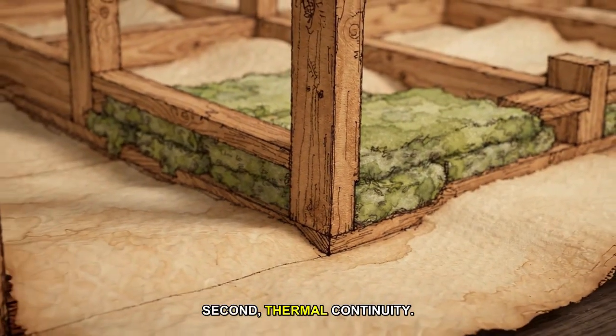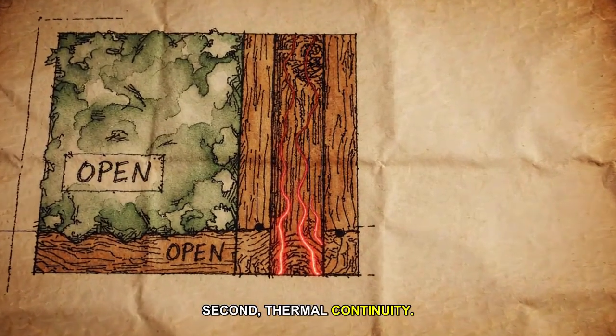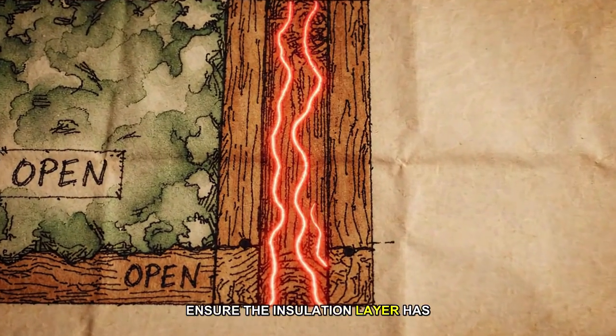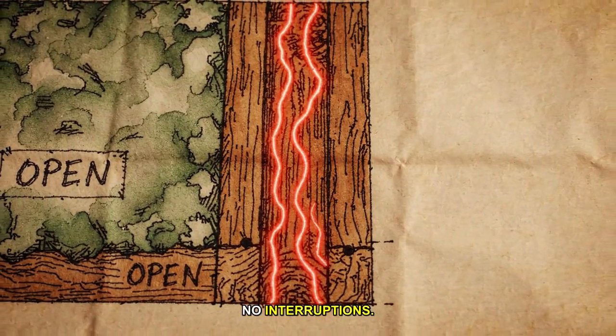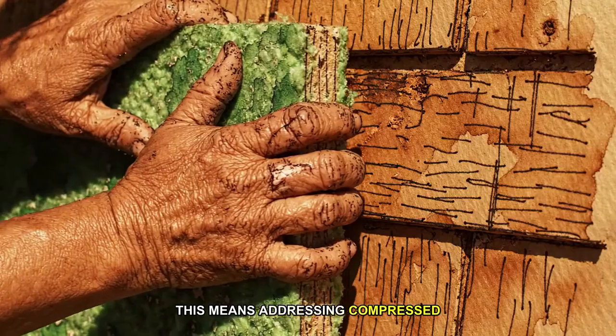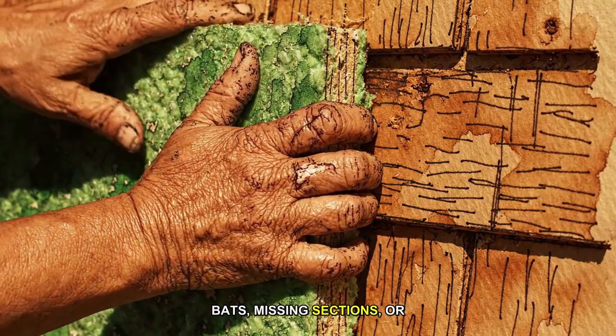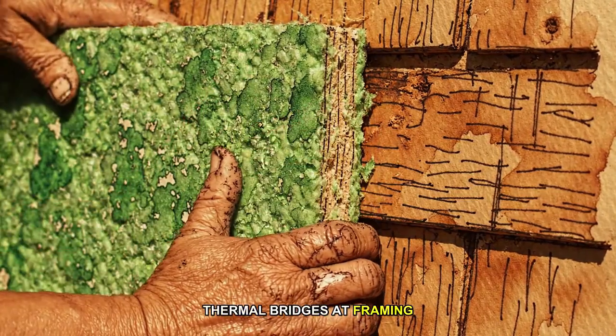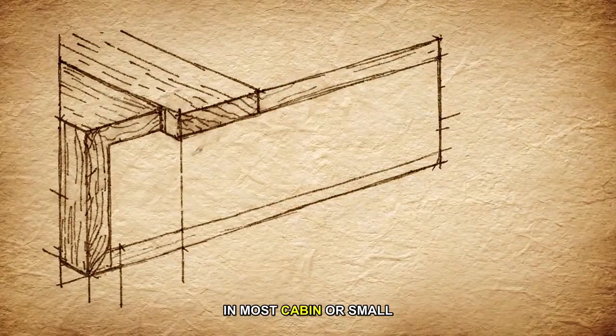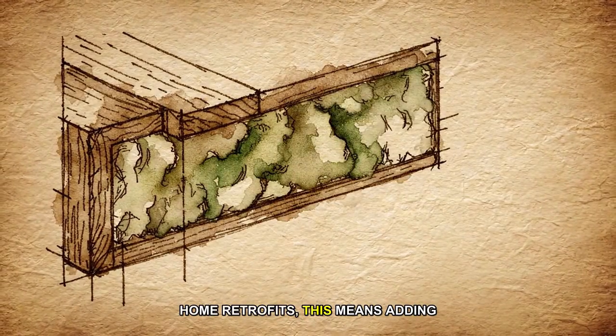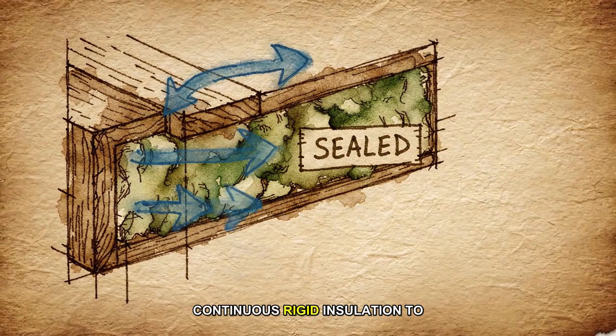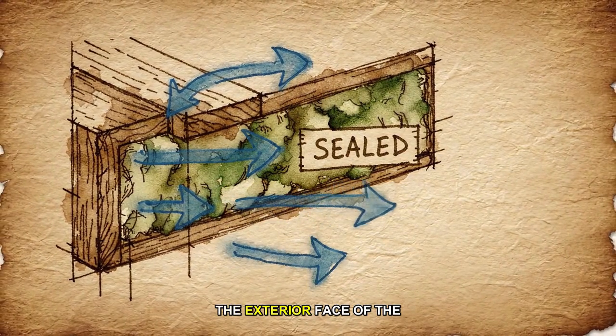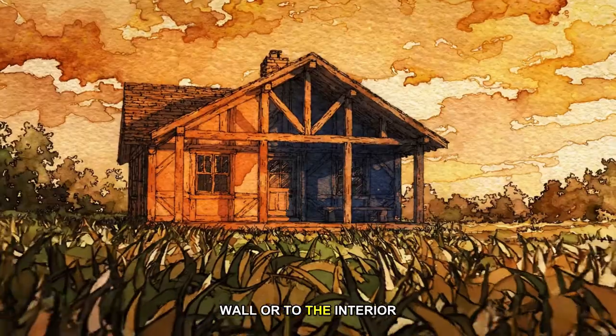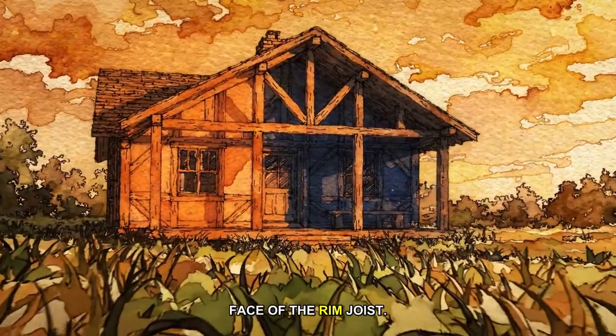Second, thermal continuity. Ensure the insulation layer has no interruptions. This means addressing compressed batts, missing sections, or thermal bridges at framing members. In most cabin or small home retrofits, this means adding continuous rigid insulation to the exterior face of the wall or to the interior face of the rim joist.